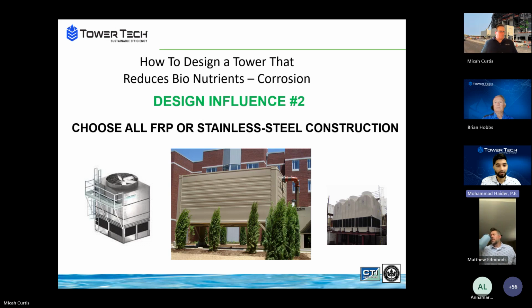It's not about a condition of, okay, let's maintain the tower. No, it's not an if, it's a when you get corrosion on the tower. So choose a design that is fully resistant to that, that doesn't have dissimilar metals, so it's not galvanized plus stainless, or just galvanized itself. You're either going to go with a stainless steel tower, which will last a lot longer compared to galvanized, or you'll go with an FRP or some sort of polymer tower design, which are 100% corrosion resistant. With FRP, you're not going to get any corrosion at all because you don't have any metal in the system, and same with a polymer-based tower as well.